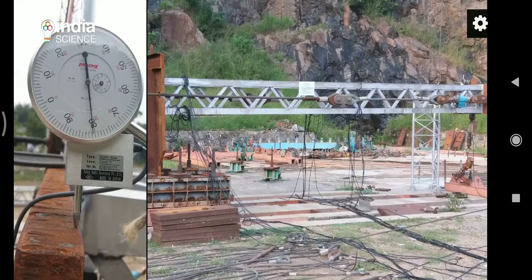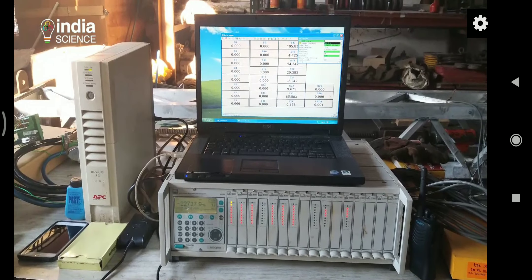The developed system has been designed using FE software and has been proof tested for the prototypes of the structures. All the elements have been tested as per international standards, ensuring that the system is structurally stable. By using this system, there are ready-made modular structures available which we have to transport to the site, and within two to three days we can be able to restore the power.